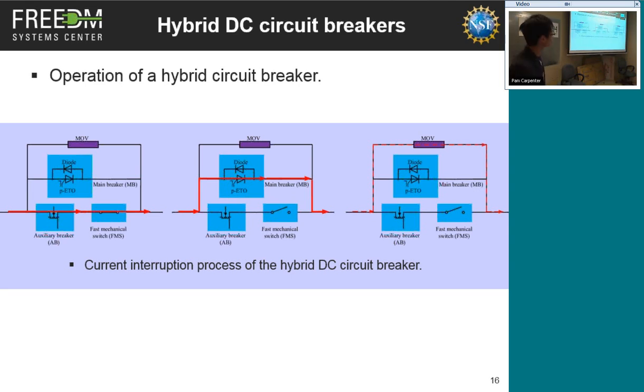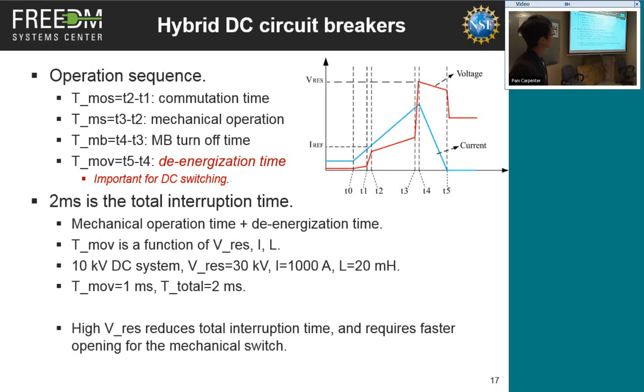So if we look at what's happening in terms of current and voltage, we notice that we can divide this whole process into a few stages. For example, the fault happens at T0, and the fault current continues increasing. At T1, you detect that and decide to interrupt the circuit. First of all, if you have an auxiliary breaker like I showed here, you turn that off first, and then the current is transferred to the main breaker, which is this path. Then your mechanical switch should be on the way to open, on the way to achieve a sufficient gap between the contacts. That would be in the period from T2 to T3. At T3, you turn off the semiconductor, the main breaker, the high voltage semiconductor.